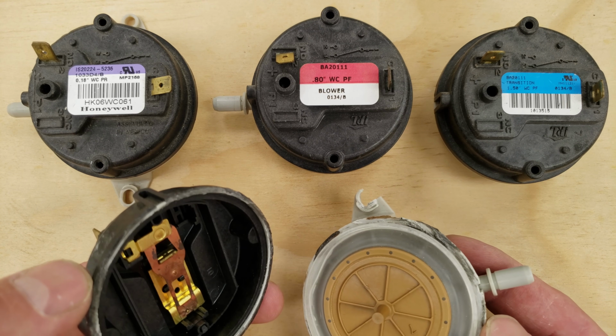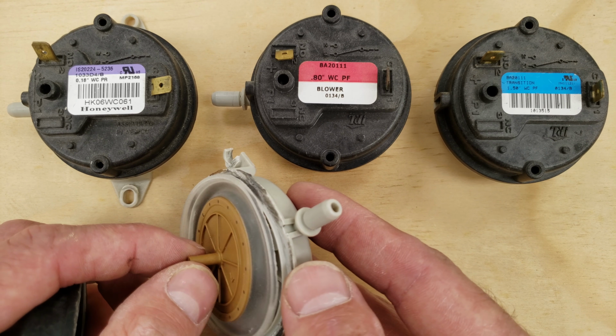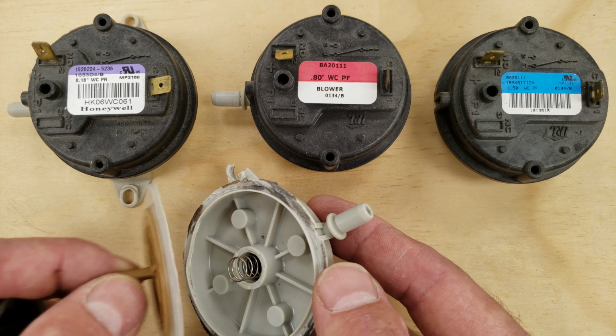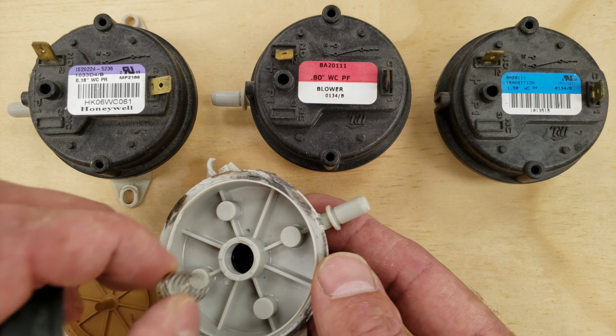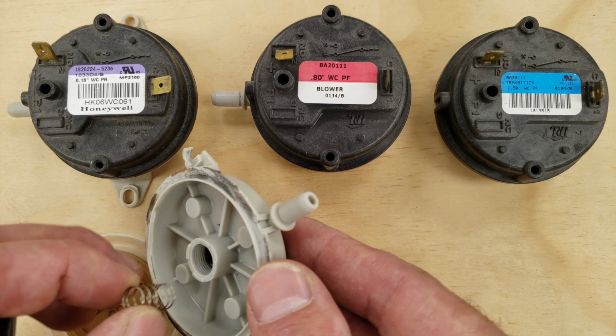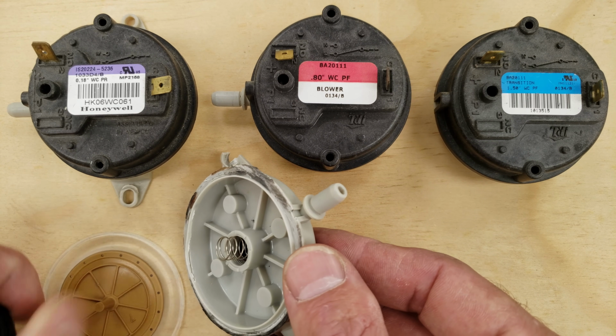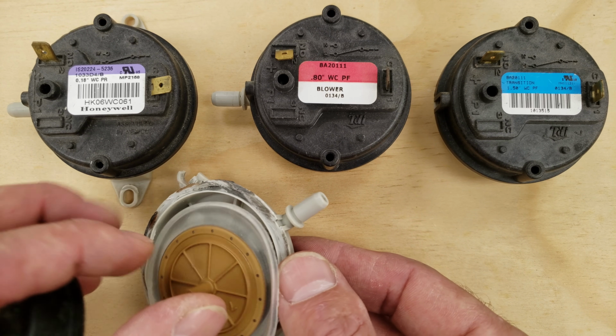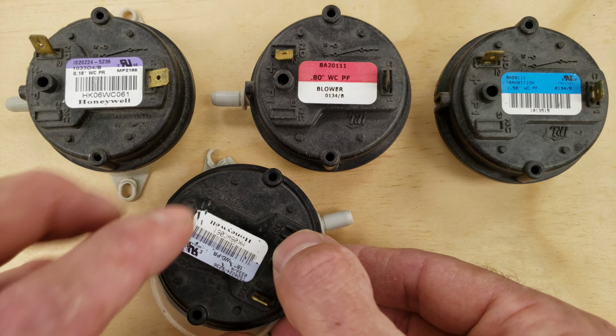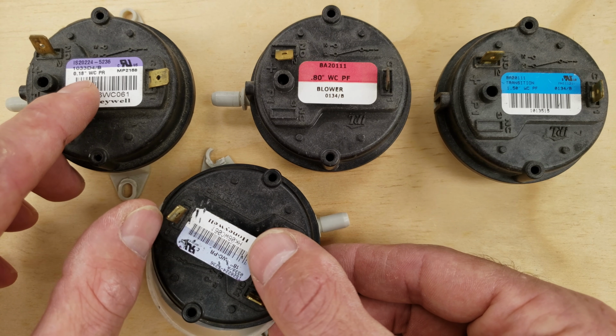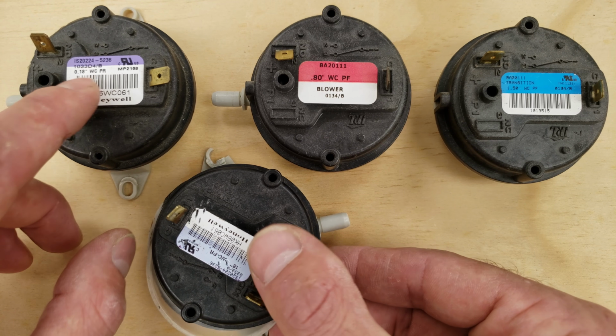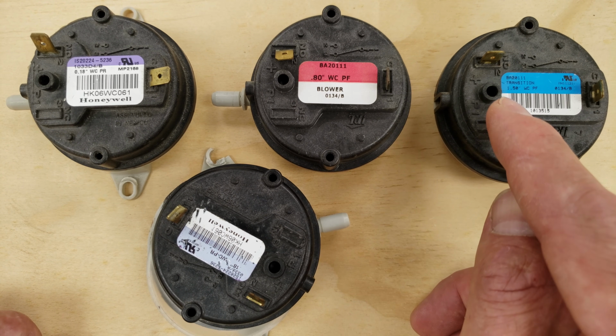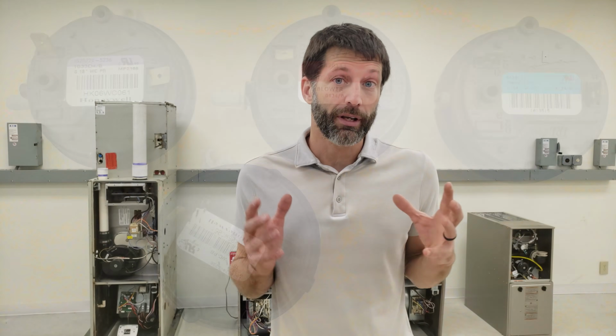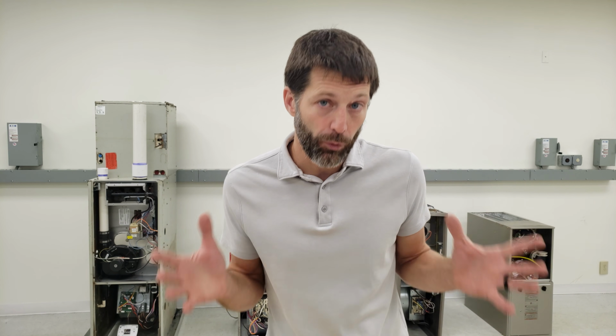So it's an air chamber here with a switch, and here you have a diaphragm separating the two chambers. Then you have a spring, and you have a little set screw down here that applies more force onto the spring. So on each of these pressure switches you have a rating right here. It says 0.18 inch water column, 0.8, and this one says 1.5 inch water column. It takes 27.6 inches of water column to equal 1 psi of pressure. So we're talking about extremely low pressures here.